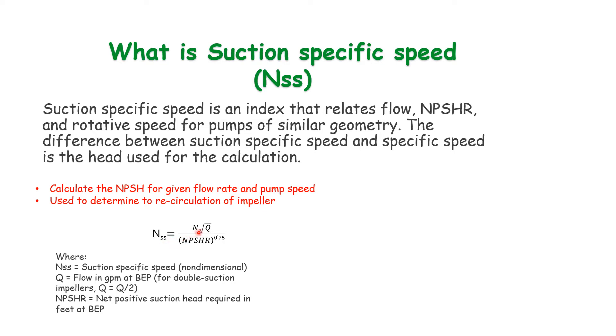Basically, NSS equals N (the speed of pump), multiplied by the square root of flow, divided by NPSHR raised to the power of 3/4. We can see that suction specific speed has a direct relationship with flow and speed of pump, but it has an inverse relationship with NPSHR.